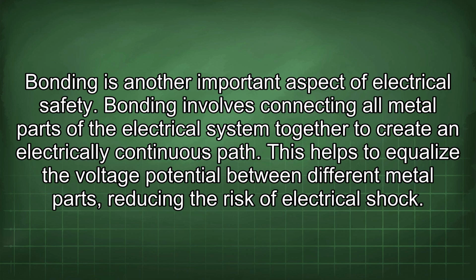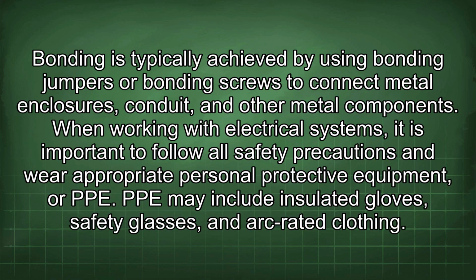Bonding is another important aspect of electrical safety. Bonding involves connecting all metal parts of the electrical system together to create an electrically continuous path. This helps to equalize the voltage potential between different metal parts, reducing the risk of electrical shock. Bonding is typically achieved by using bonding jumpers or bonding screws to connect metal enclosures, conduit, and other metal components.